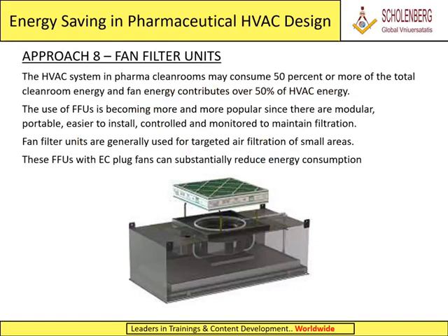Approach 8, Fan filter units. The HVAC system in pharma clean rooms may consume 50% or more of the total clean room energy, and fan energy contributes over 50% of HVAC energy. The use of FFUs is becoming more and more popular, since they are modular, portable, easier to install, controlled, and monitored to maintain filtration. Fan filter units are generally used for targeted air filtration of small areas. These FFUs with EC plug fans can substantially reduce energy consumption.